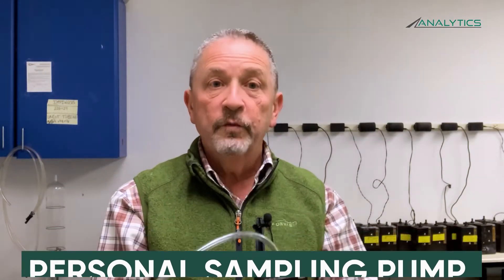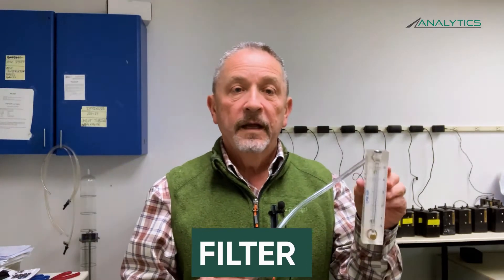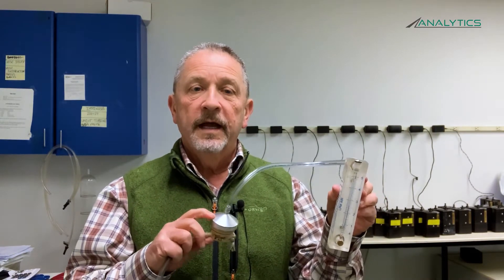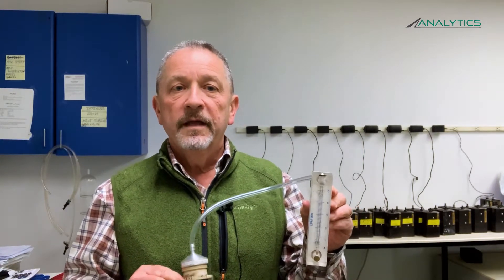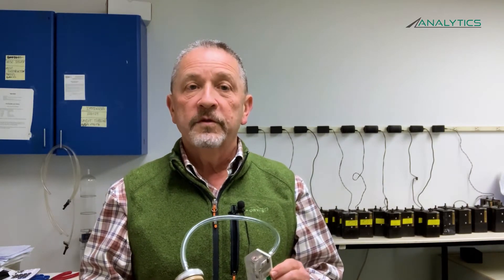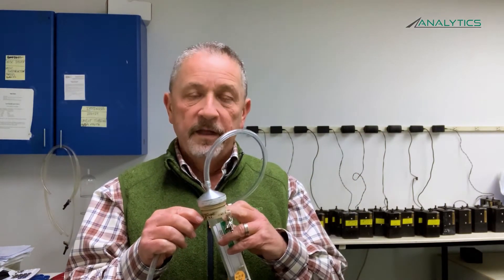The second item is a personal sampling pump. You'll notice we have a length of tubing attached to the pump, and this tubing is used to connect the pump to your parallel particle impactor. The third item is a calibration device — a field rotameter connected to a parallel particle impactor with a calibration adapter. If you purchase your PPIs from Analytics Corporation, we can provide you at no charge a personal sampling pump, and we pre-calibrate the pump for you at our laboratory, then send it to you along with the field rotameter, calibration adapter, and the PPI setup.